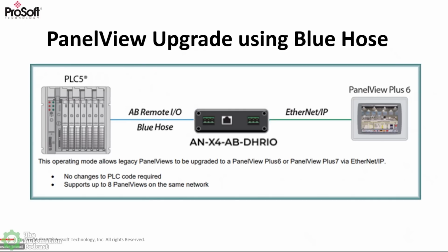The big thing here is not having to change the program in your PLC5. It was block transferring to a panel view, maybe rack 5, group 0 through 7, and you don't want to change that. But you do have to replace the old screen—maybe it's broken, maybe somebody put a hammer through it. So how do you take a new panel view plus 7 or 6 on Ethernet and have it emulate that old remote I/O panel view?